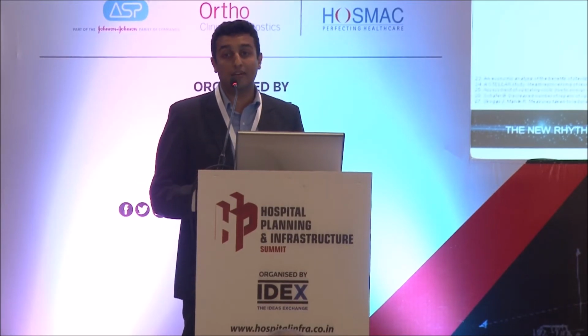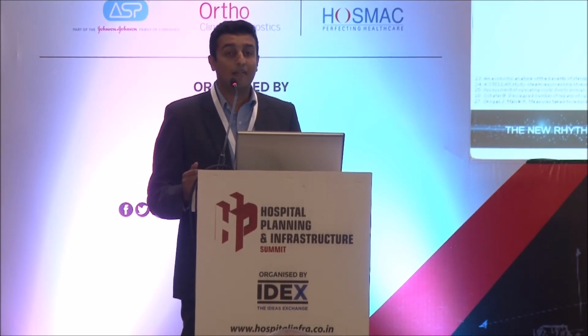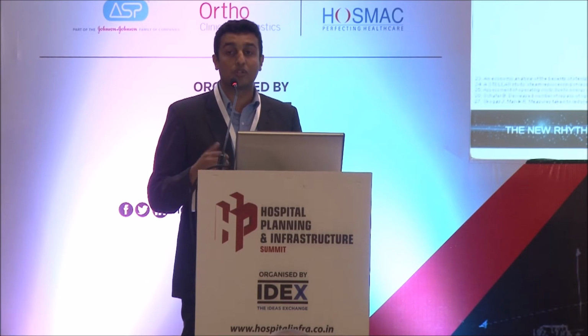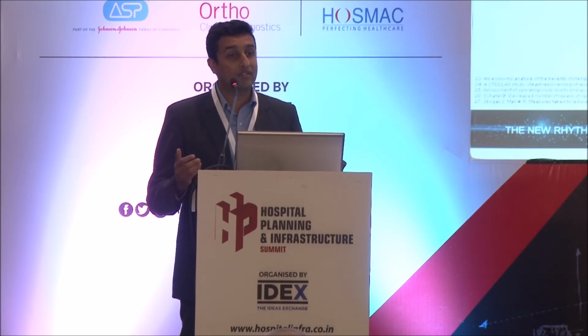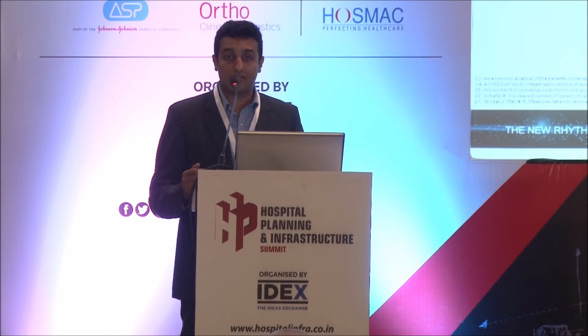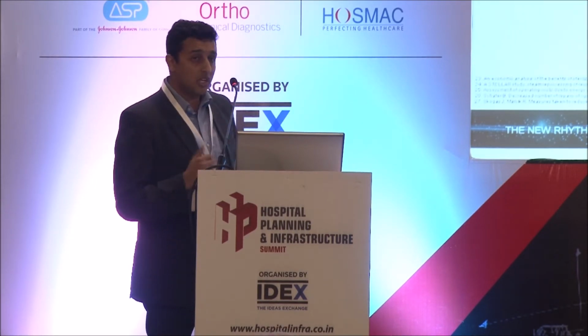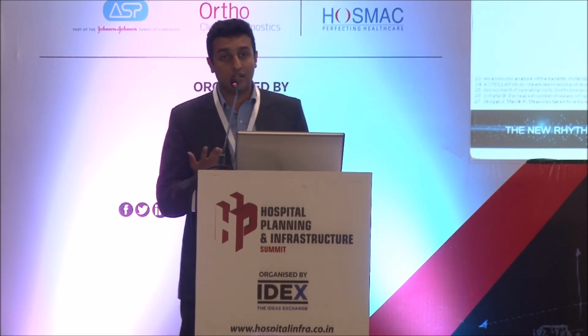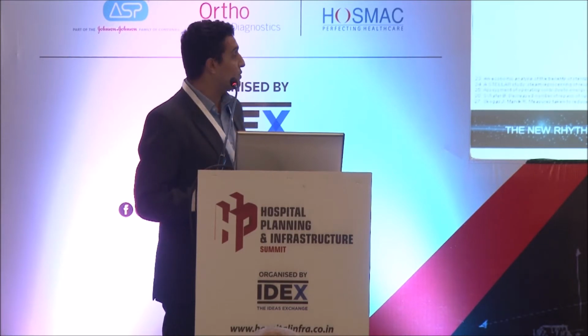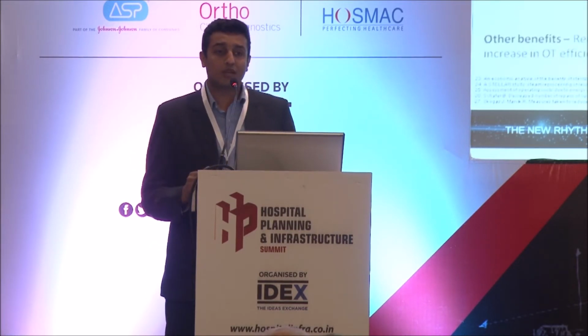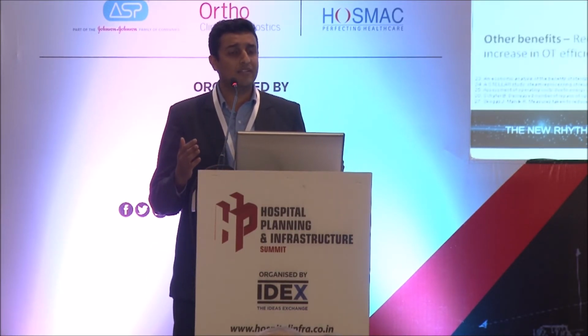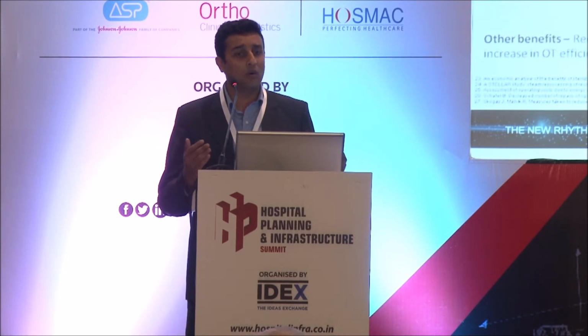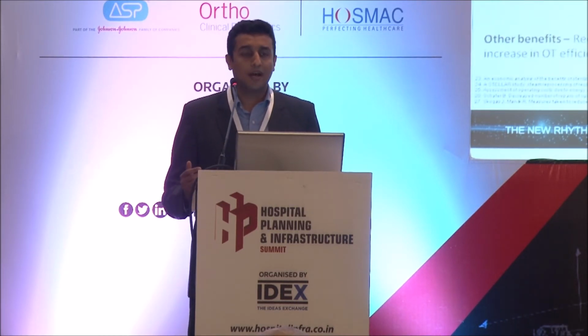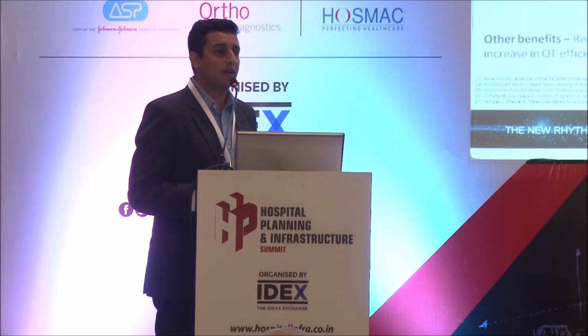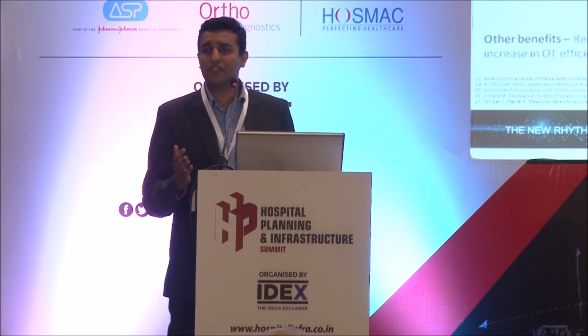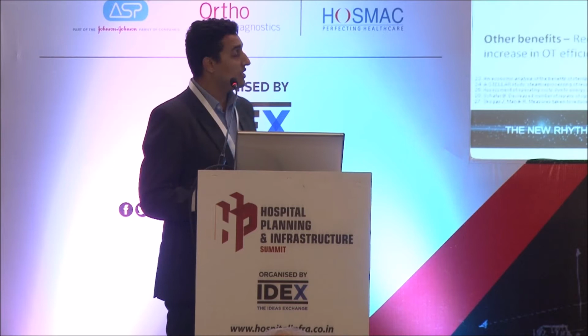That actually, for a country like India, gets saved. The power required to run an ethylene oxide sterilizer for almost 10 to 12 hours gets saved. Energy cost, whether it's steam or EO, is a great saving from that perspective. And there are other benefits: for any hospital, CSSD, a steam autoclave or an EO unit requires a huge amount of space. The plasma sterilizer that I'm talking about requires a space as big as a refrigerator in your CSSD.